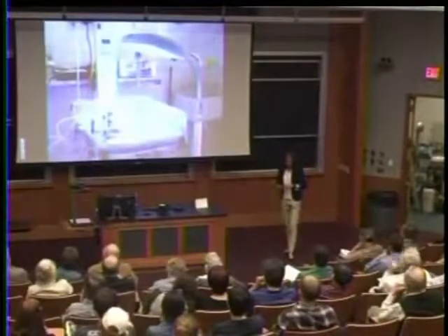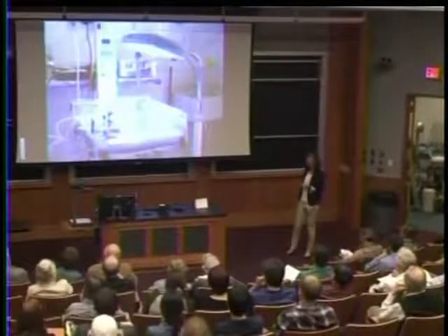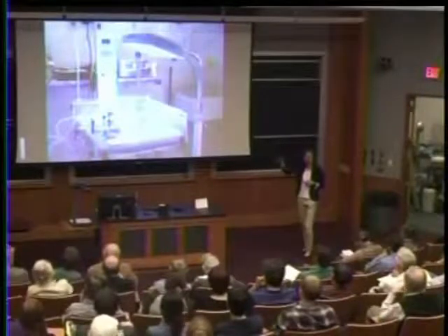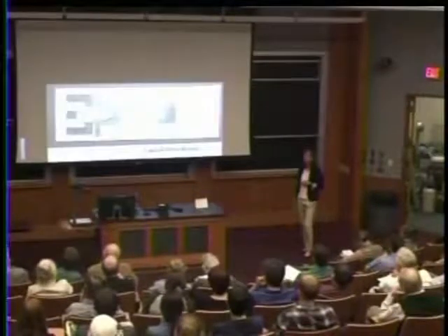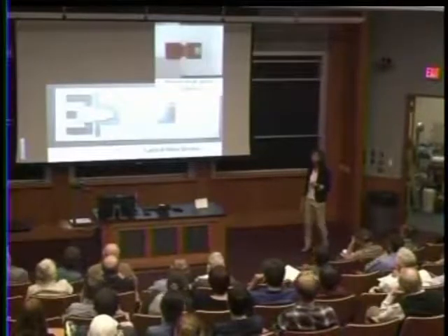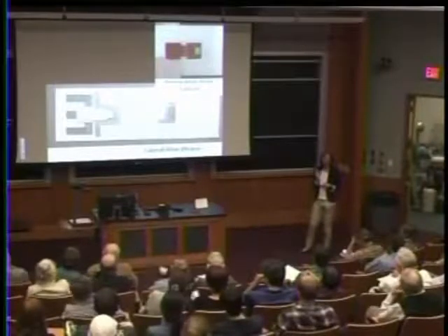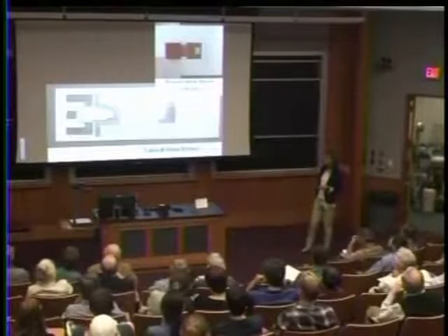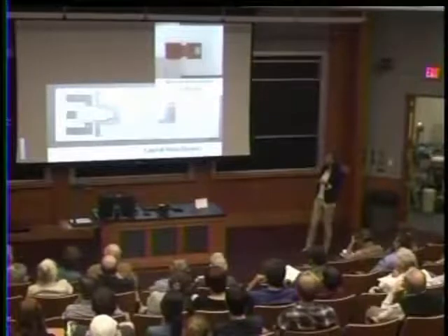And so I wanted to show you just in the last couple of minutes some of these technologies that are under development. This is a technology that's made by an organization called D-Rev in the Bay Area. It's an LED-based set of phototherapy lights to treat neonatal jaundice. We're working on a point-of-care diagnostic to monitor serum bilirubin. You need to be able to separate out the hemoglobin because its absorbance spectra is so much stronger than that of bilirubin. And so again, we've made a little paper and plastic device that allows you to spot a drop of blood and separate out the hemoglobin.